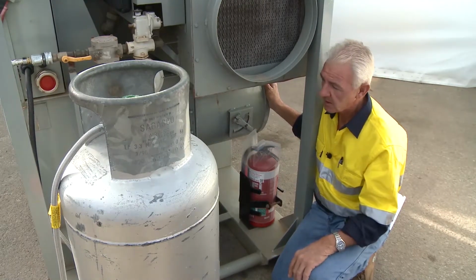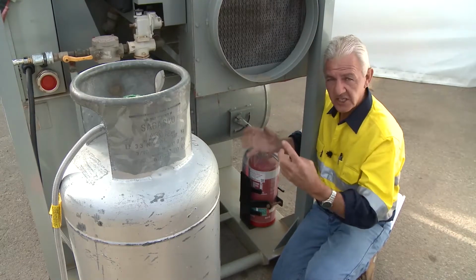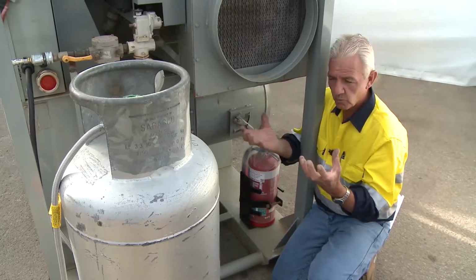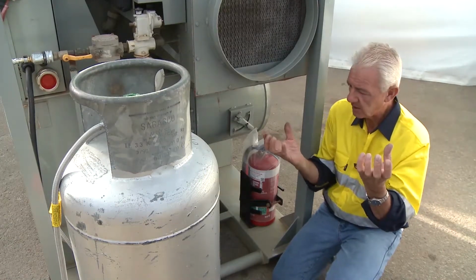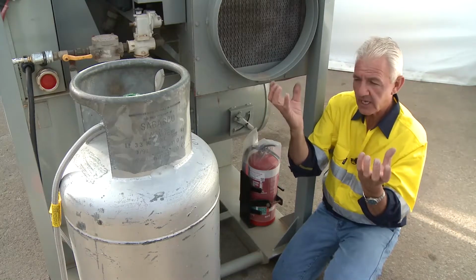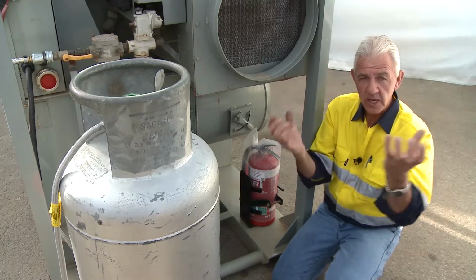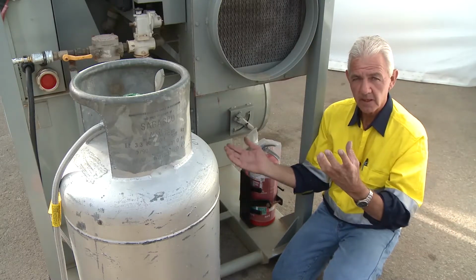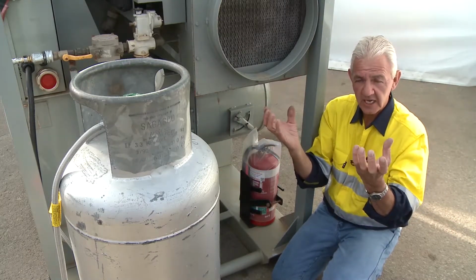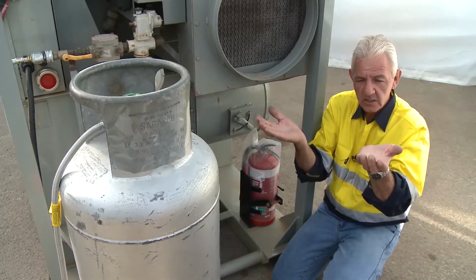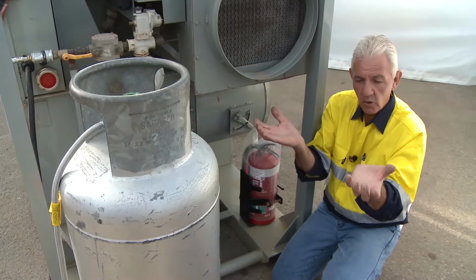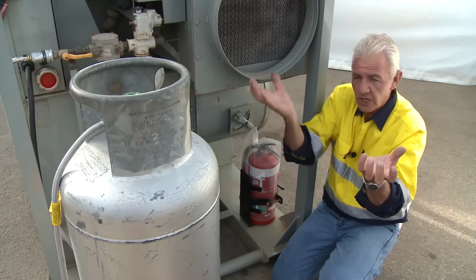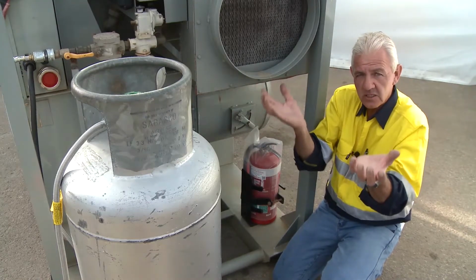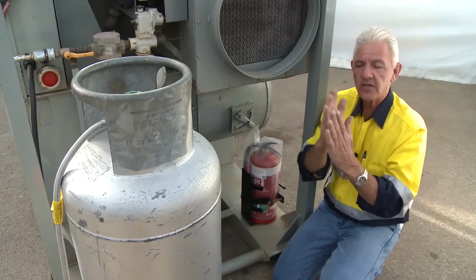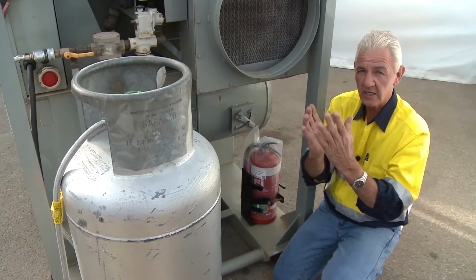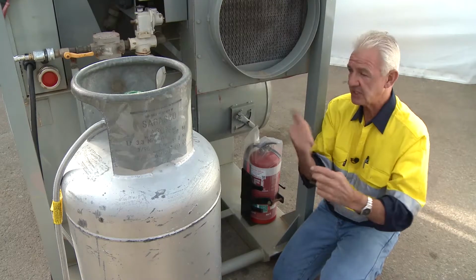So when we start the machine and show you what that should look like, you'll go, oh yeah, that's relatively simple. So the equalisation of air, what we're doing for the machine is pumping one side up and holding the other side back, so that we get an equilibrium of air. Instead of it flowing through one side and just exhausting, the desiccant wheel doesn't have time to process that air. So it's sort of like a weight and measure. If we push the air in one side and hold the other side up to give it a balance of air in and air out, then the desiccant wheel spinning around, taking the moisture out, has the capacity to process that correctly and send it out the other side.